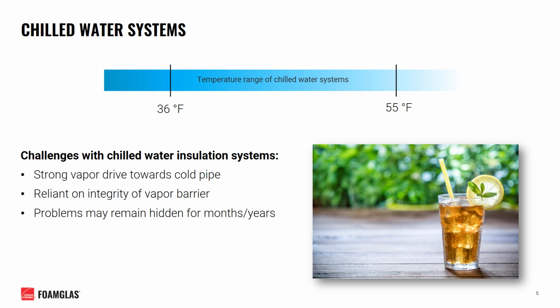If you've ever had a cold beverage out on a hot summer's day on a patio, you're already familiar with the phenomenon we're going to be talking about extensively here today, and that is condensation and moisture buildup all along that cold pipe surface. And this condensation can bring about a variety of challenges for the insulation system on that cold pipe. We're going to be talking today about strong vapor drive into and onto that cold pipe surface underneath the insulation, and that'll bring about an emphasis on the performance of the insulation system's vapor barrier.